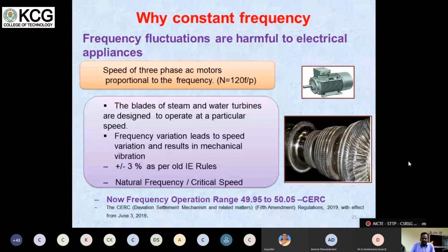If the frequency is more, that means what? There are conditions why the frequency is more, that we'll see. When the frequency is more, our turbine blades, particularly LP turbine blades, low pressure turbine blades, will have problems due to centrifugal force. They will get damaged. So not only on the appliances side, we have problems on the generator side also. At the same time, if the frequency is low, then the turbine will get problems. It will go to the critical frequency, or what is called the natural frequency. Below some frequency, the turbine will have more vibrations.